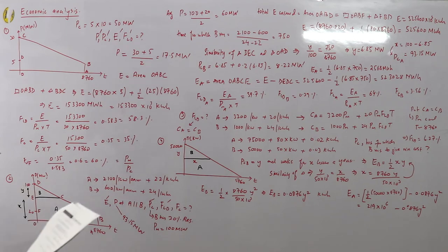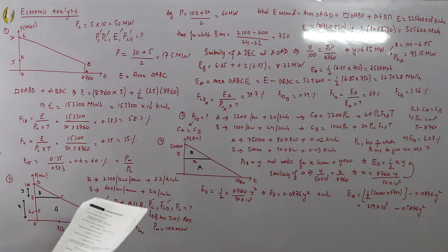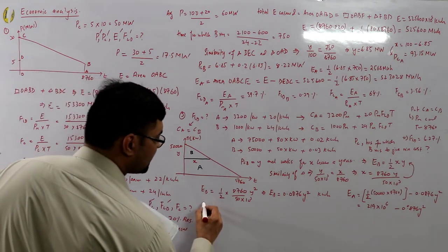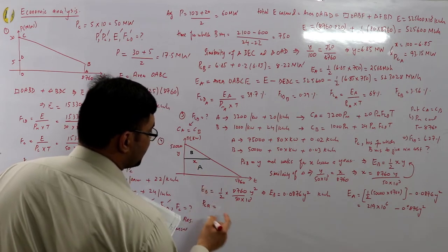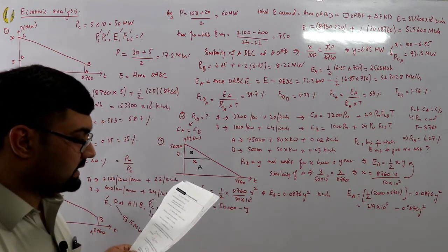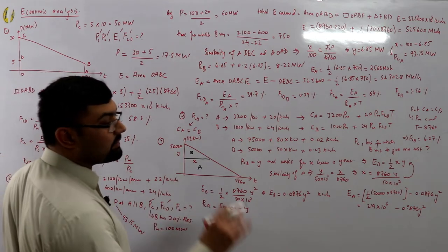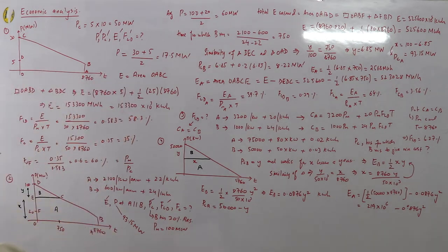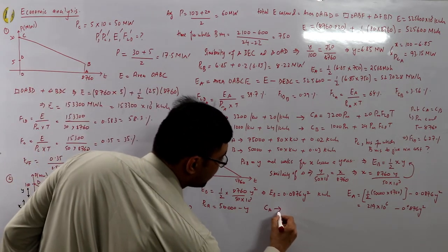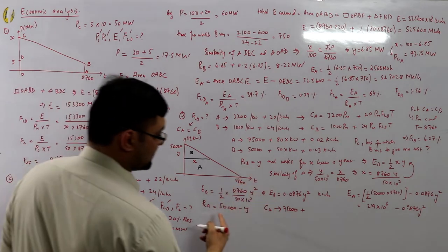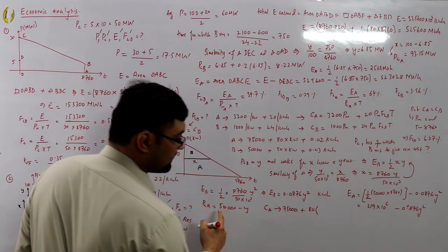Okay. So from the load duration curve, the installed capacity of B is Y, I've already told you. And the installed capacity of A would then be 50,000 minus Y, in terms of kilowatts. Now I have the kilowatts for them and I have the kilowatt hours for them. So the cost model CA would be 75,000 plus 80 into kilowatts, so 80 into 50,000 minus Y.